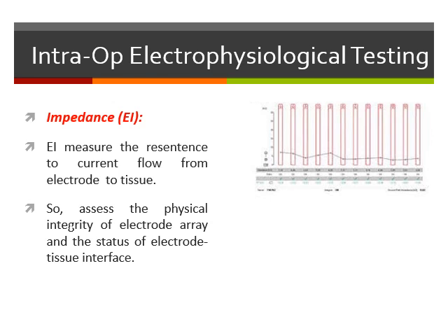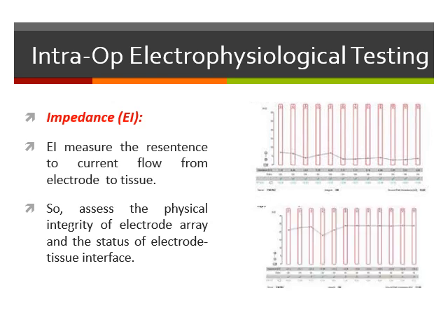Low impedance means that the electrode is in contact with a medium with excellent or very good electric conduction, which is most probably, in such a case, the perilymph. So now I can make sure that all the electrodes are in contact with fluid or with perilymph.